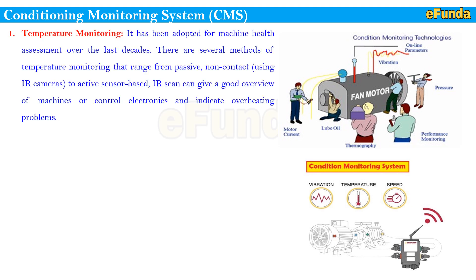First critical parameter is temperature monitoring, which has been adopted for machine health assessment over the last decades. There are several methods ranging from passive or non-contact type using IR cameras, which can give a good overview of machines or control electronics and indicate overheating problems. Contact measurement is very useful for early detection of lubrication-related problems.